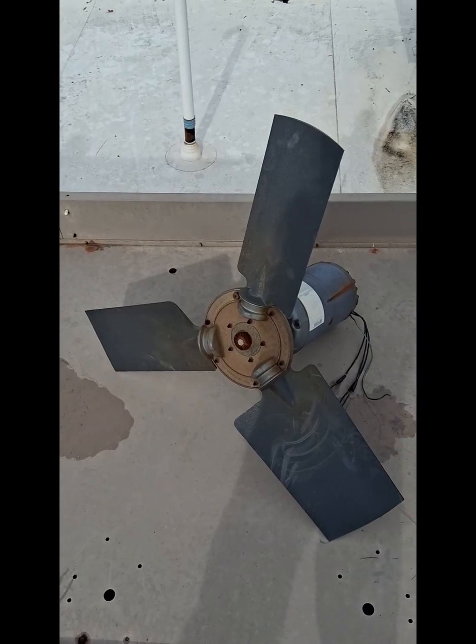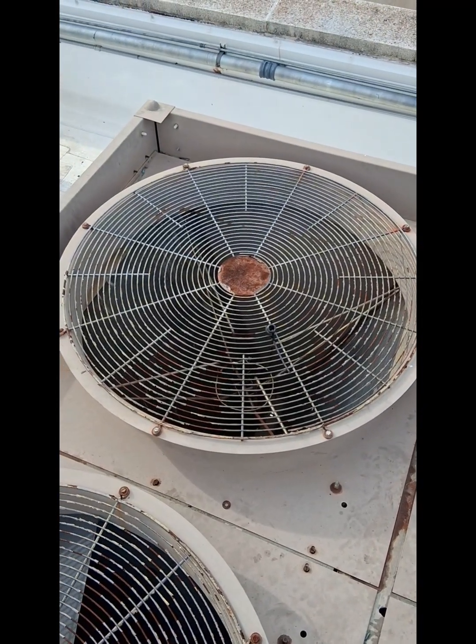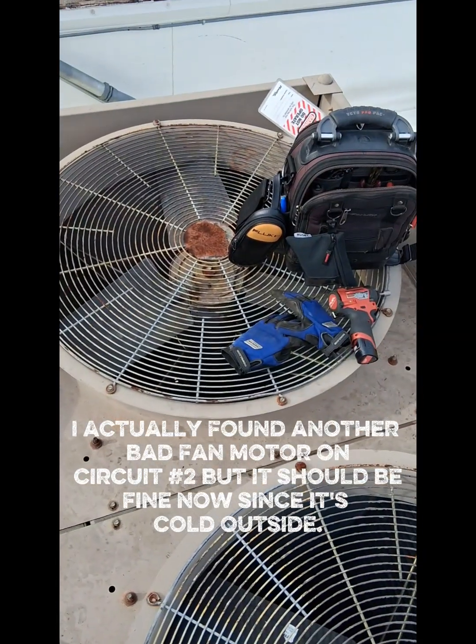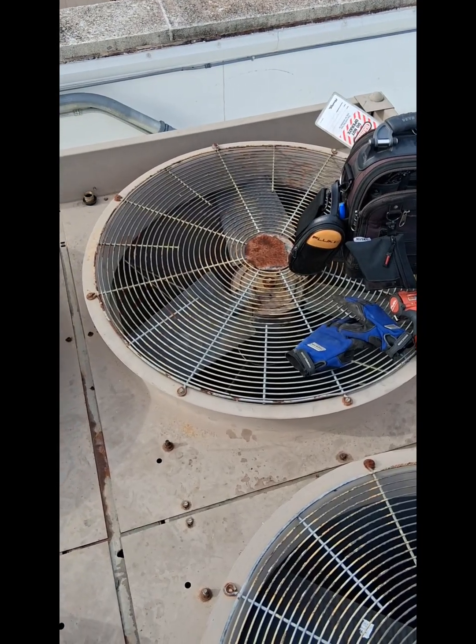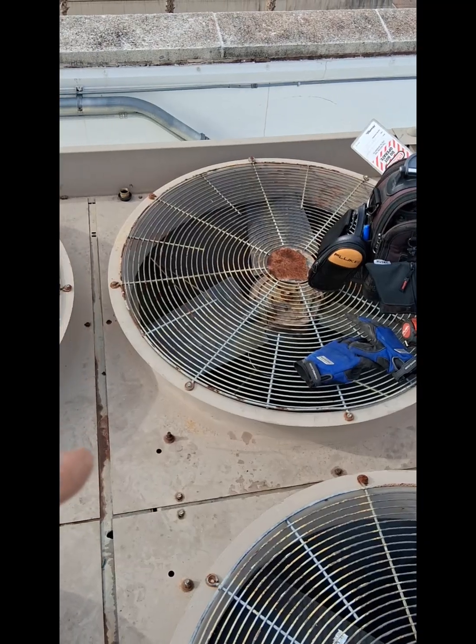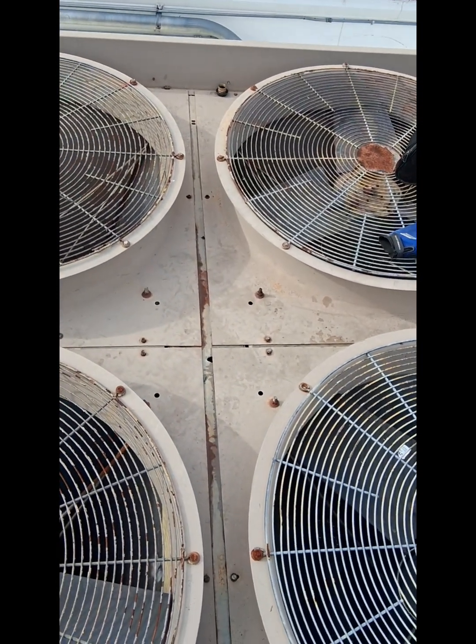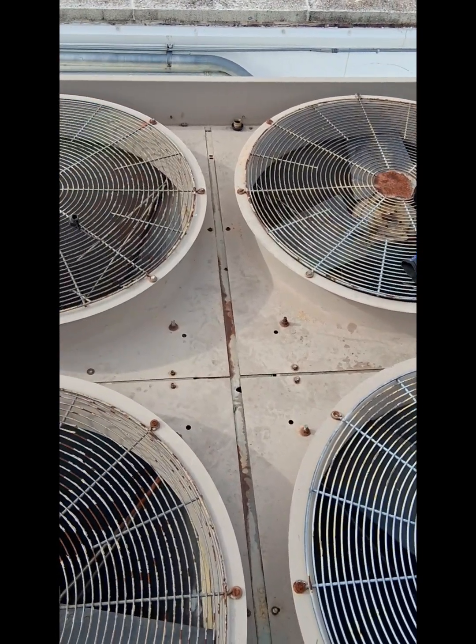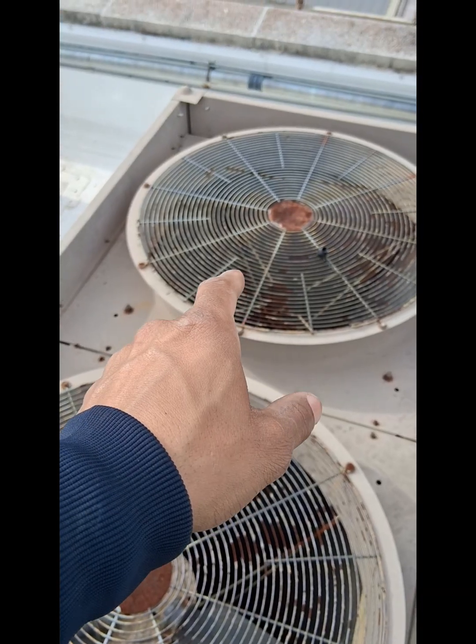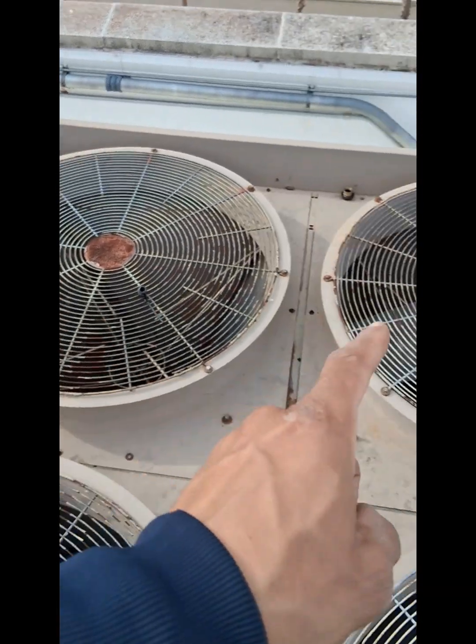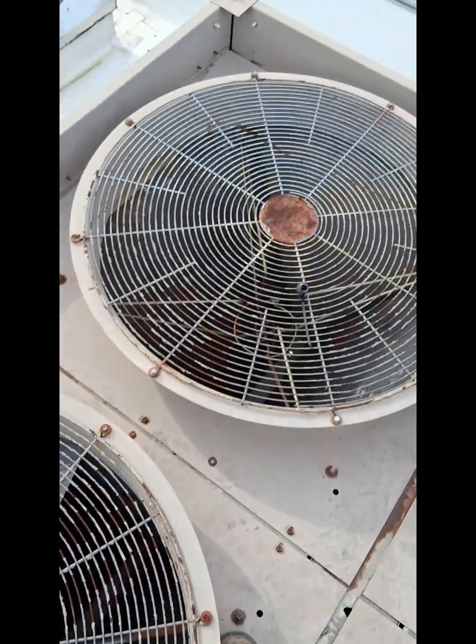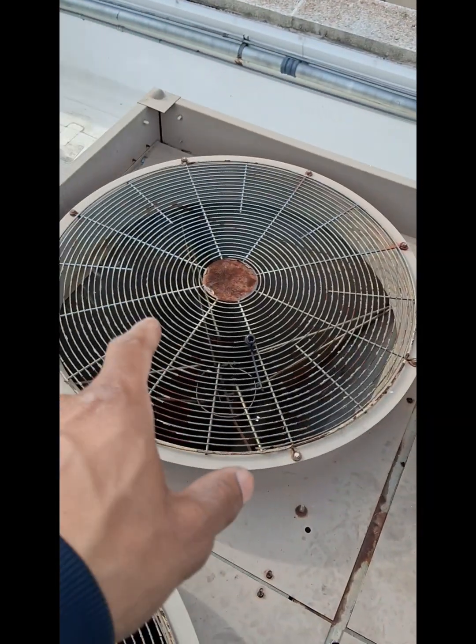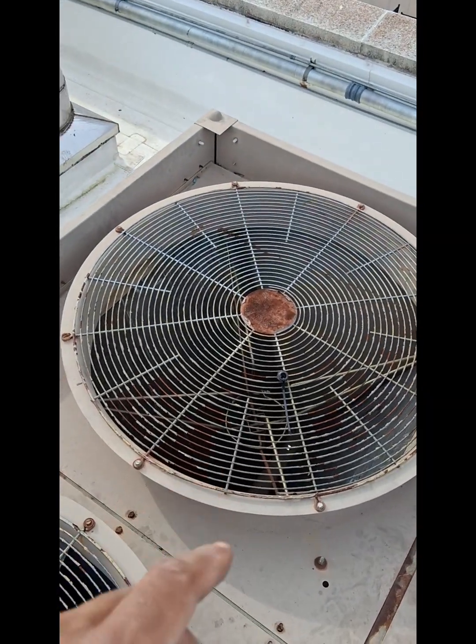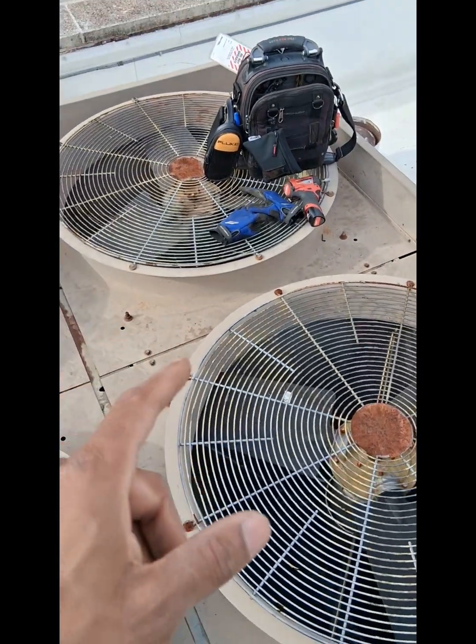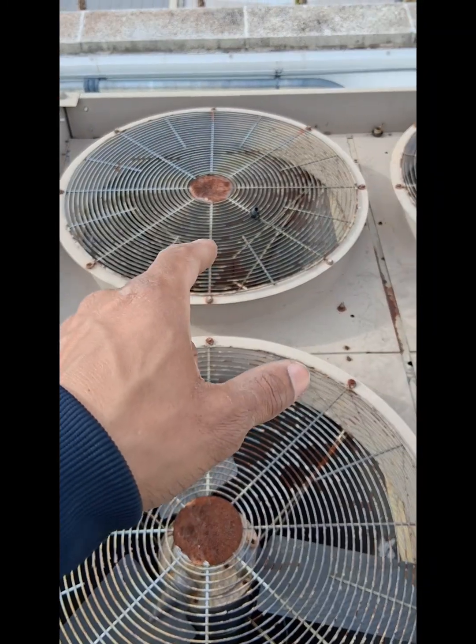To get the system up and operational, I had to remove the fan motor from circuit number 1 and place it on circuit number 2 because circuit number 1 was running fine. The only problem is the VFD fan motor is not operating correctly, and it had 2 blown fuses from that motor being failed. So I took the good motor from that circuit because it has a bad discharge pressure transducer reading 0, so it's not allowing this fan to come on. So I placed it over here. I have the bad fan motor right here. I've taped up the wires for circuit 1. So instead of putting a new fan motor on that circuit, we're gonna put a new fan motor on this circuit, as well as a discharge pressure transducer to get circuit 1 back up and running. But now they'll have at least circuit 2 running and operating until somebody can get the repairs done on this circuit.